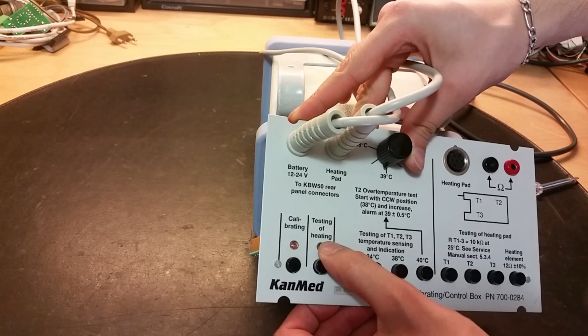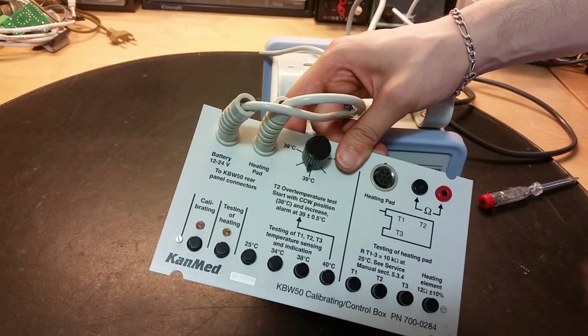Yes, on this test panel, we've got testing of heating and calibrating. And we've got this heating pad, it looks like that, kind of. We put the baby on the heating pad because babies cannot regulate body heat so well. We've got this little knob here that can fine tune the heating, actually 40 degrees, that goes up here. And we can also do an over-temperature test. So you don't want to cook the baby, you want to just warm it up a bit.